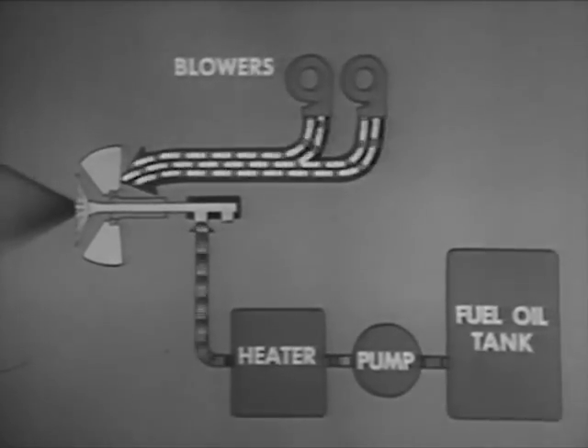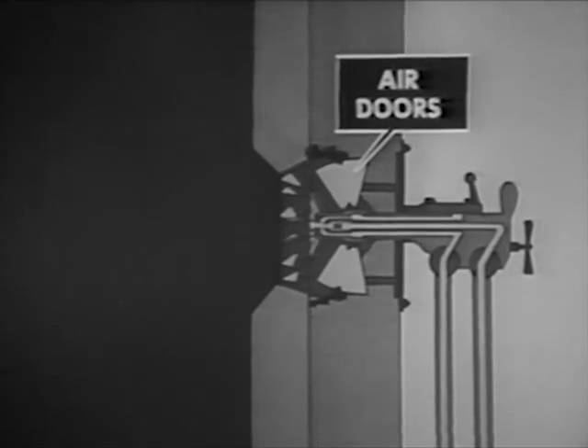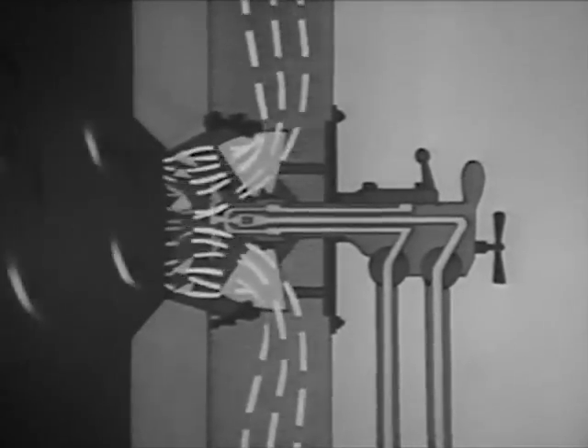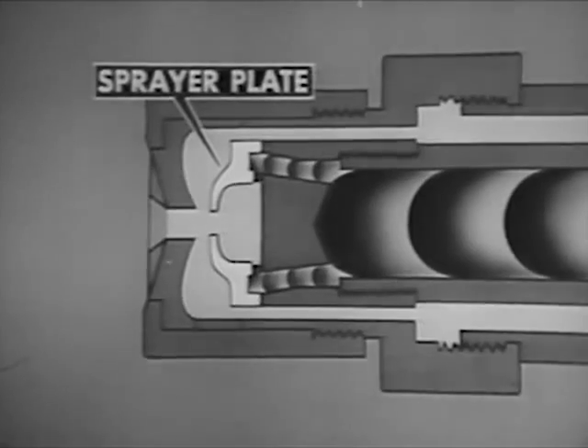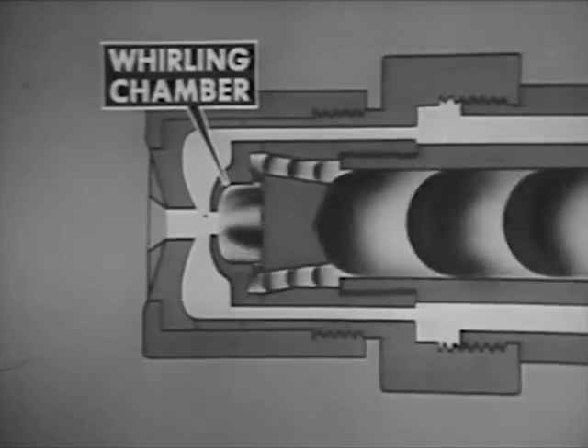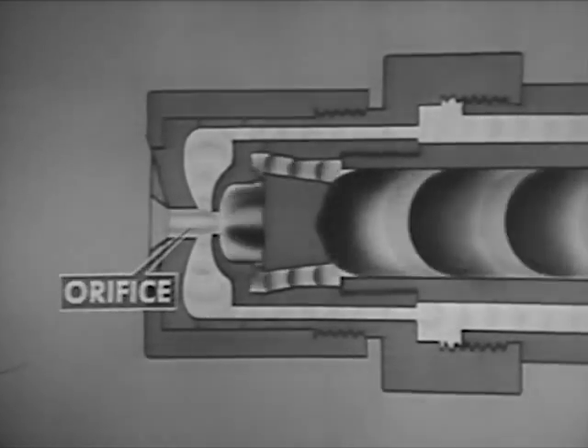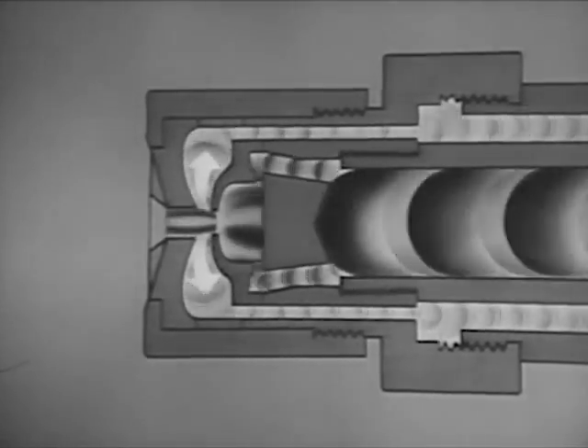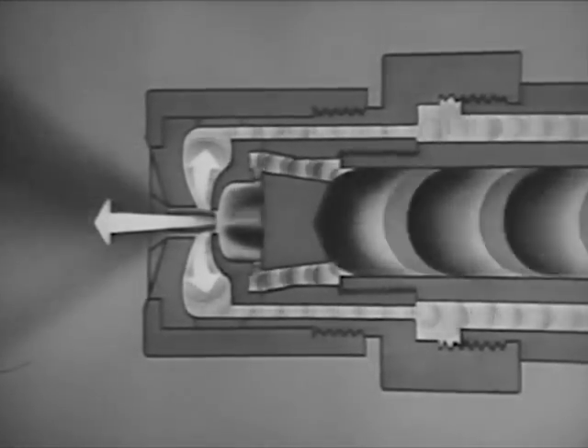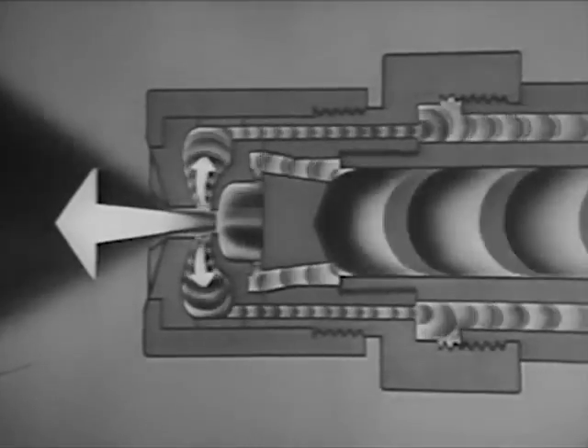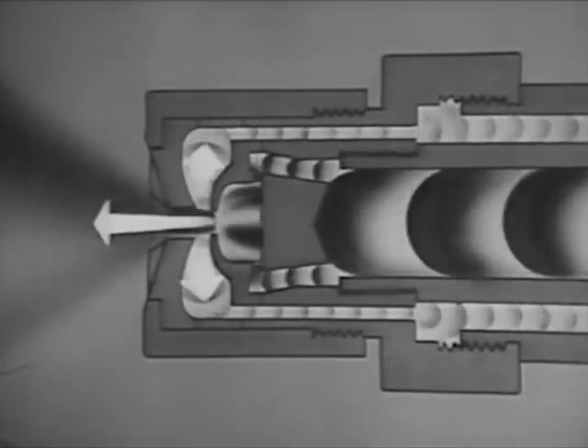In this type burner, only part of the oil that goes through the burner is actually burned. The remainder returns to the fuel oil pump. Air doors and a bladed cone give the whirling motion to the air that enters the register to mix with the oil, as in the burner seen previously. The oil, heated and under pressure, is forced through the inner tube of the burner barrel to the sprayer plate, where the oil is rotated in the whirling chamber. The oil leaves through the sprayer plate orifice. Centrifugal force sends some of the oil into the return line and back to the fuel oil pump. The remaining oil continues through the orifice into the furnace. At the burner's maximum firing rate, practically all the oil enters the furnace. At the minimum firing rate, practically all the oil returns to the pump.